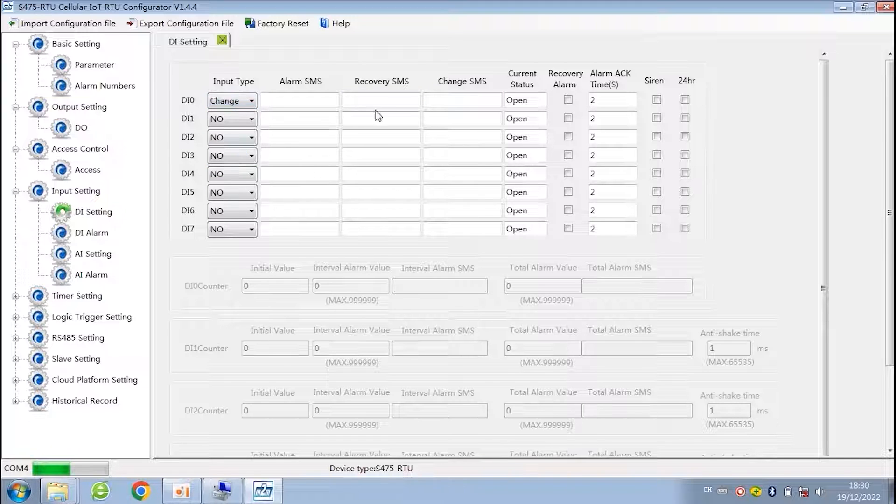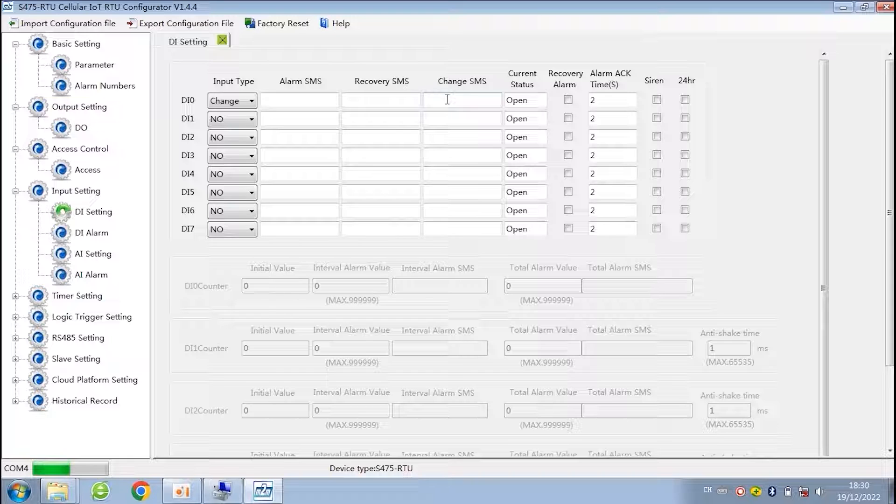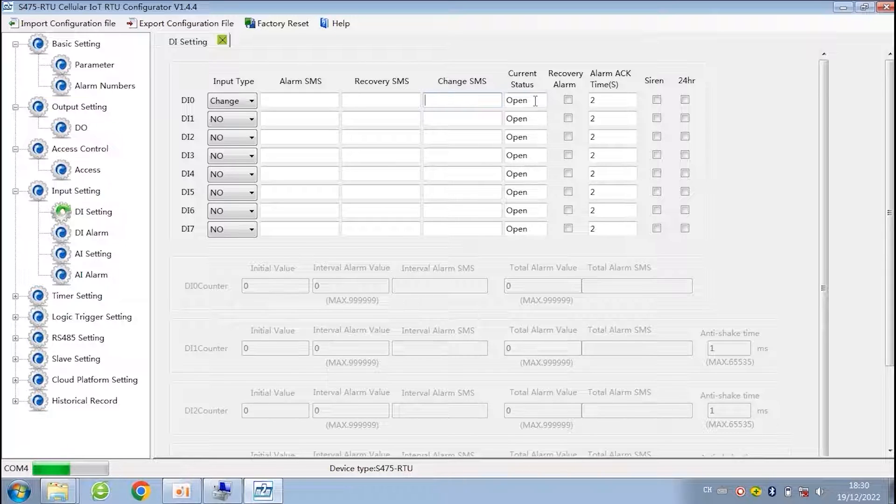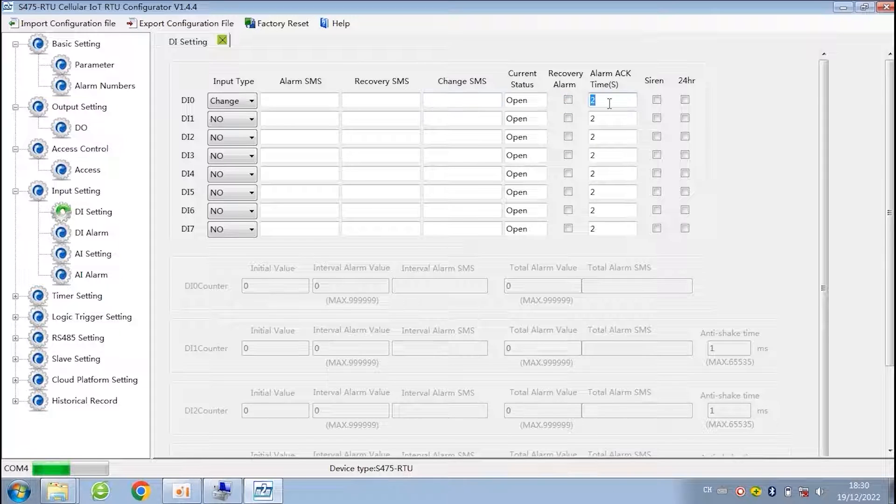If you choose change, once the status of digital input changed, the alarm will be triggered. The alarm ACK time means only when the states changed more than this time, it will be treated as a true alarm.